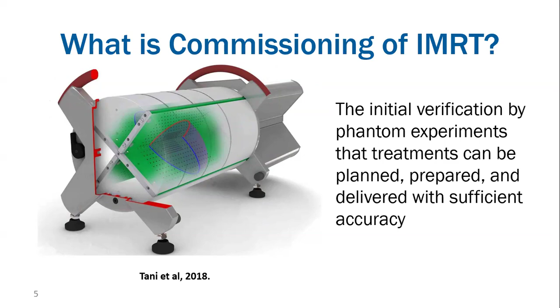So what is the commissioning of IMRT? In medical physics, we use the word commissioning to mean a lot of different things in different scenarios. So it's always good to specify in the beginning whenever you're talking about commissioning what exactly you're talking about. And in the context of IMRT, it means the initial verification via phantom experiments that the treatments can be planned, prepared, and delivered with sufficient accuracy. And we'll basically be going into each component of that as we go through the talk.